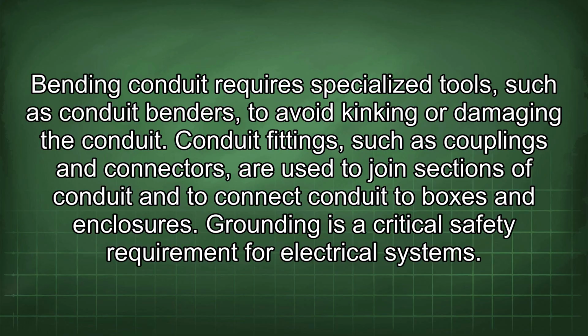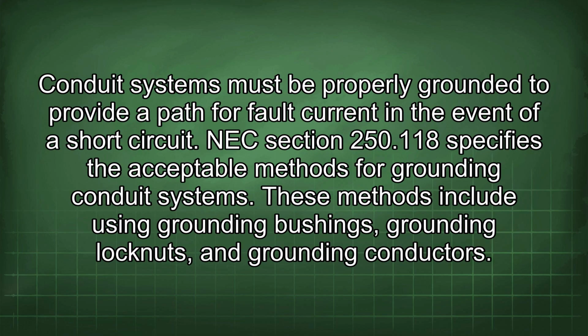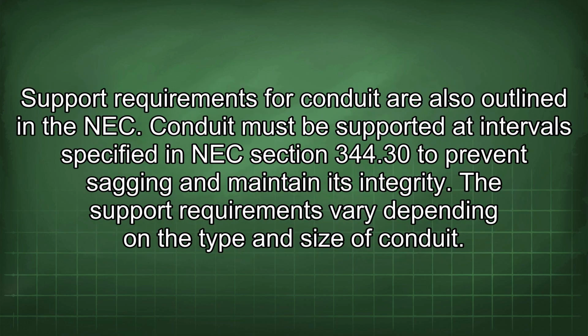and enclosures. Grounding is a critical safety requirement for electrical systems. Conduit systems must be properly grounded to provide a path for fault current in the event of a short circuit. NEC Section 250.118 specifies the acceptable methods for grounding conduit systems. These methods include using grounding bushings, grounding lock nuts, and grounding conductors. Support requirements for conduit are also outlined in the NEC.